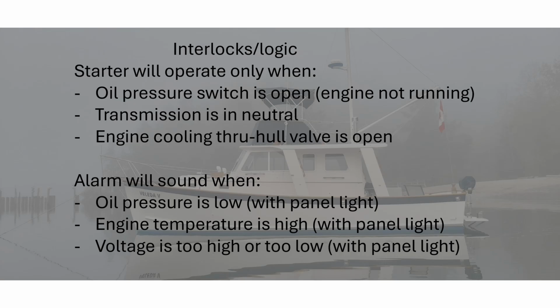Set up the interlocks so that the starter will only operate when the engine is not running, and that's controlled through the oil pressure switch. The engine has to be in neutral and the cooling valve has to be open. So I had to add limit switches for those, and you'll see those in later slides.